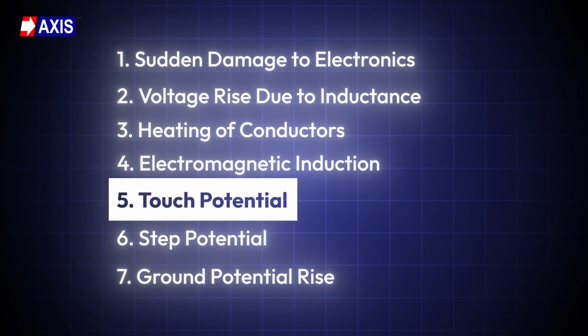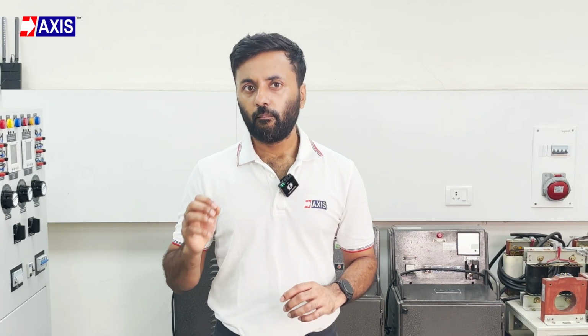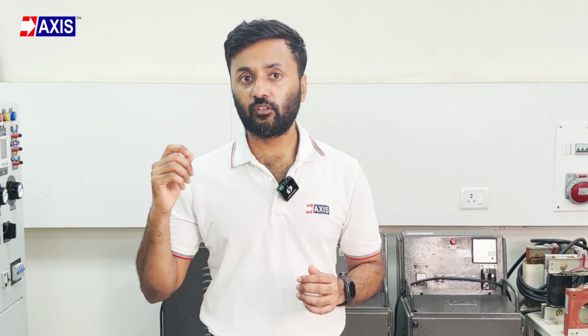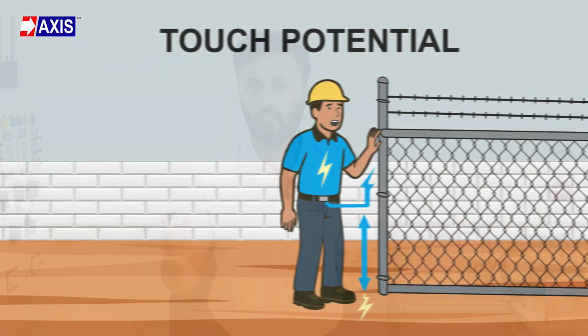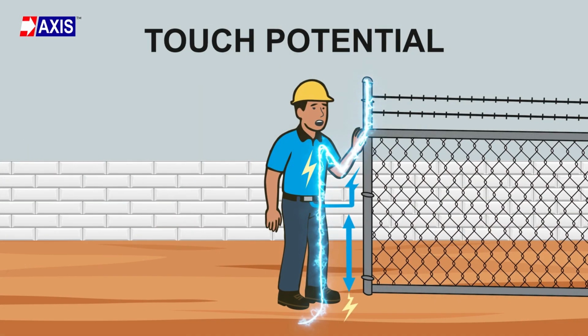Fifthly, touch potential. There may be no visible damage, but during or just after a strike, if someone touches a down conductor or any metal part such as a railing, gate, or pipe, they might feel a shock or a burn. This happens because the metal part is at a different voltage than the ground or nearby surfaces. When lightning strikes close by, the current spreads through the ground and the metal, and for a few seconds, the two connected surfaces may not be at the same voltage. If someone touches both at the same time, the current can pass through their body. This sign tells us that some parts of the structure are not bonded properly. It becomes a serious safety risk during a strike.